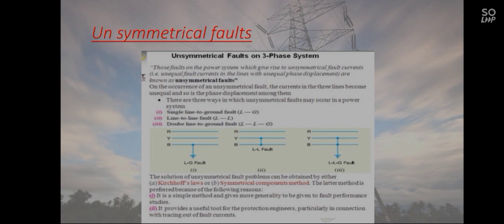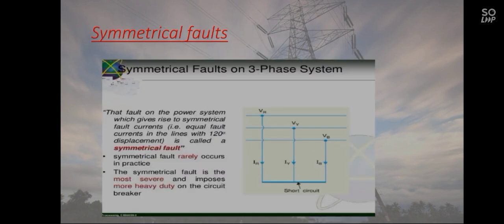The solution of unsymmetrical fault problems can be obtained by either Kirchhoff's laws or the symmetrical component method. The latter method is preferred because of the following reasons. It is a simple method and gives more general results for fault performance studies. It provides a useful tool for protection engineers, particularly in connection with tracing out the fault current.